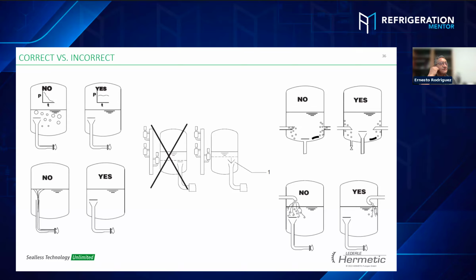Some companies use bypasses, meaning they open a bypass to return the liquid back to the vessel. The disadvantage of the bypass is you don't control the pressure. You need a constant pressure on your hand expansion valve. With the bypass, you reduce the pressure. The same way with the frequency drive. Some companies reduce the hertz on the pump to reduce the speed of the pump and reduce the flow.